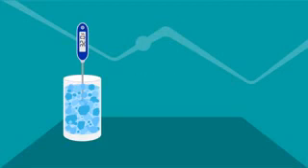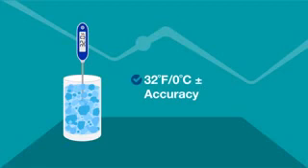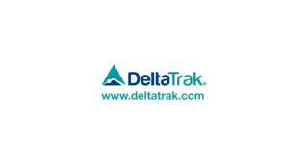The display should now read 32 degrees Fahrenheit or 0 degrees Celsius. Note that it can be slightly above or below this reading depending on the accuracy of the unit. Visit us online for more information on product specifications and troubleshooting.